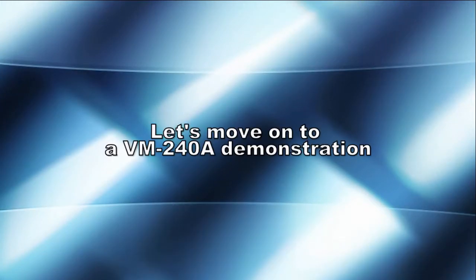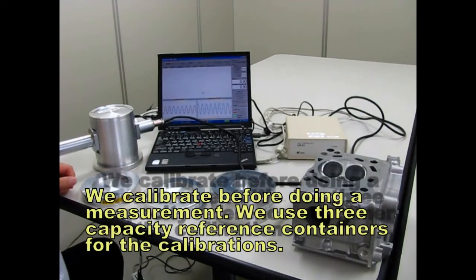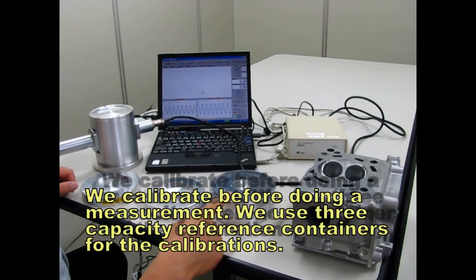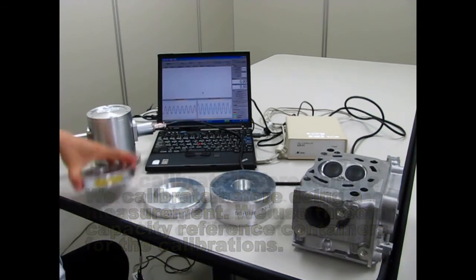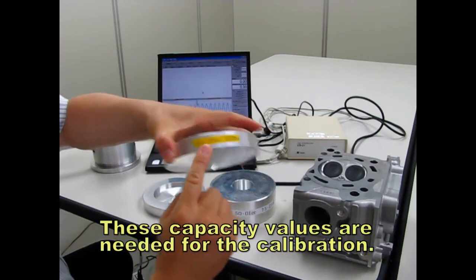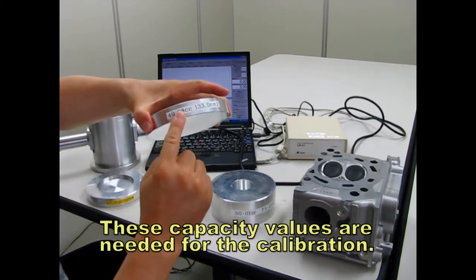Let's move on to a VM240A demonstration. We calibrate before doing a measurement. We use three capacity reference containers for the calibrations. These capacity values are needed for the calibration.